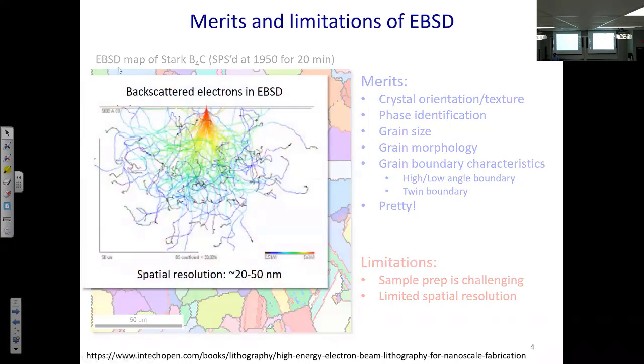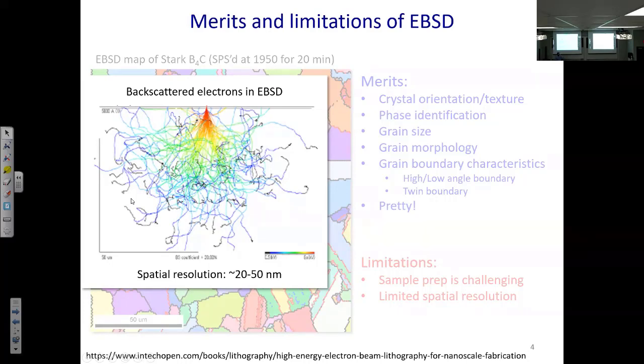Those are the advantages of EBSD in an SEM, but there are intrinsic limitations. The first is sample preparation, which is time-consuming and effort-demanding — in microscopy we say 'rubbish in, rubbish out.' The second limitation is spatial resolution, which is fundamentally limited because in SEM the electron beam interacts with a volume larger than the focused probe — like hitting one bowling pin and affecting the surrounding pins. This limits EBSD spatial resolution to roughly 20–50 nanometers depending on beam settings.